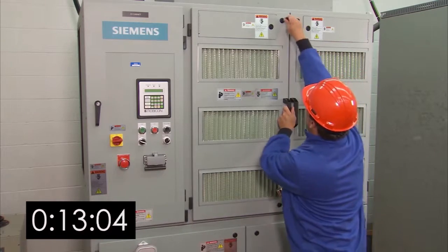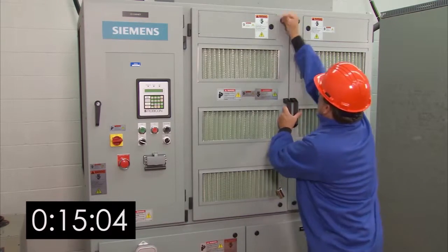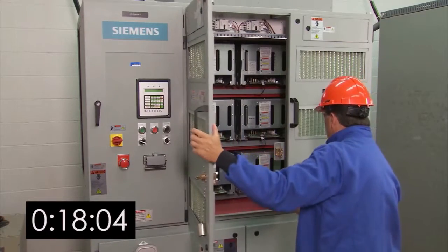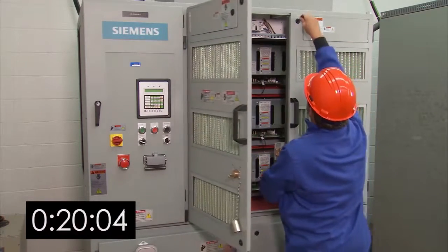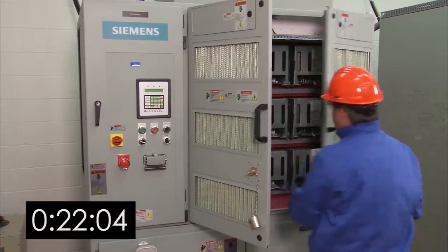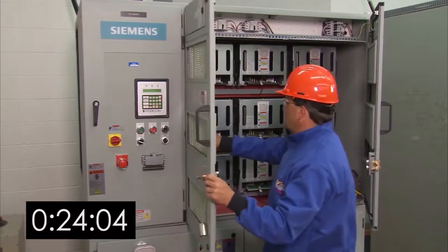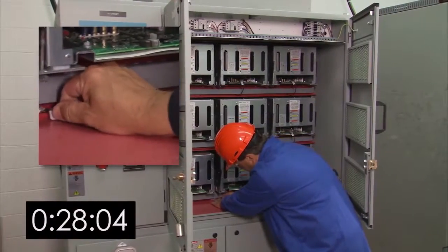Verify that all the pre-charge lights are off, then remove the fiber optic link connection. Secure it in a location where it will not be in the way when you're pulling out the cell assembly.